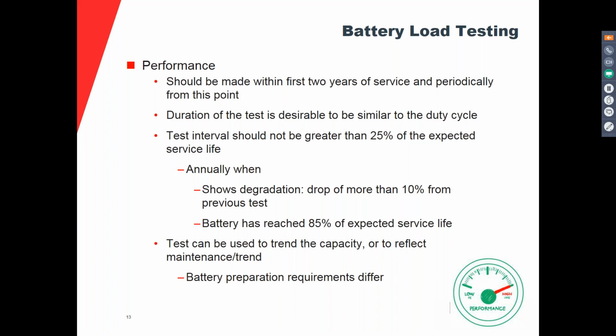This value is the one that we trend, and it's also an indicator of the maintenance. If we see that the battery is degrading faster, probably the maintenance practices are not good or the operating conditions are not good, and this can evidence the situation easily. Or it could also be an indication of a battery manufacturing process that might not be the best. So always try to look for a very good battery when you install something in your substation or your facility.